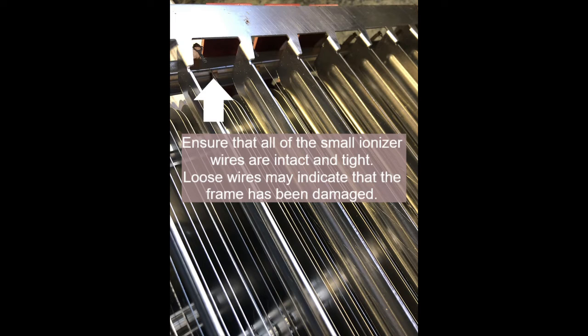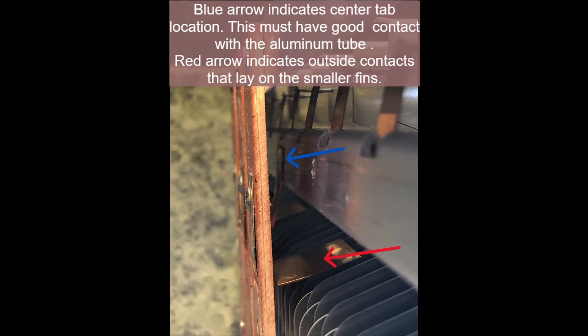Turn the filter over and locate the small ionizer wires in between the larger fins. Ensure all 9 wires are intact and that they are tight. If several are loose, check the filter frame for damage that has it out of square. Locate the contact pad on the side of the filter. Check that the contacts are clean and ensure the center contact is making solid connection with the aluminum tube that the wires connect to. Without this, it will go into a wash every time.